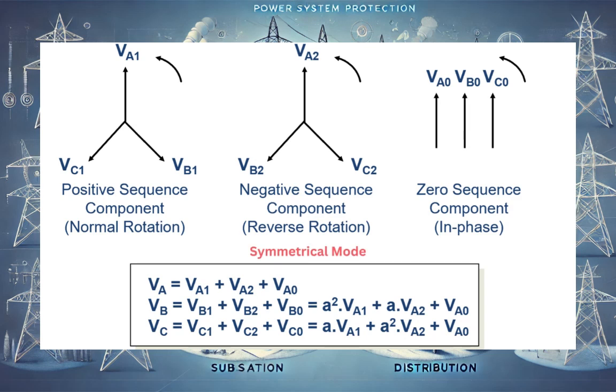Mathematically, VA = VA1 + VA2 + VA0, and VB is defined similarly with VB1, VB2. Instead of manually calculating every single time, the fault calculator's symmetrical mode helps the user to simply enter values — like two volts zero sequence, five volts negative sequence, six volts positive sequence — and the calculator automatically calculates VA, VB, VC values and populates them into the test screen. This is a very important feature that helps users test relays easily.